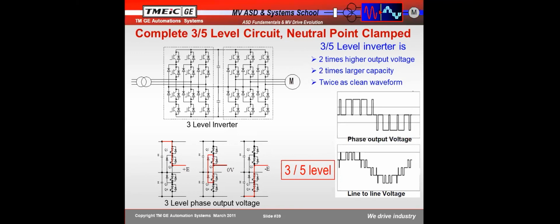Now, my opinion, here again, other people might disagree with me, but I would stand by this, that a 3-level drive is okay for 2,300 volts. Anything above 2,300 volts, I think a 3-level drive is just not cutting it these days. And 3-level drives still can cause voltage problems, especially at 4160, 6600. And you have to worry about the length of the cable between the drive and the motor and so on. So on a 2300 volt drive, I'm okay with the 3-level. Higher voltage, I really would like something better.